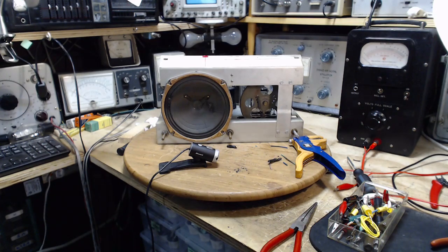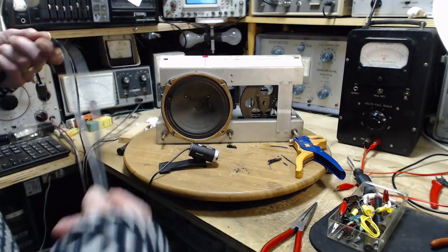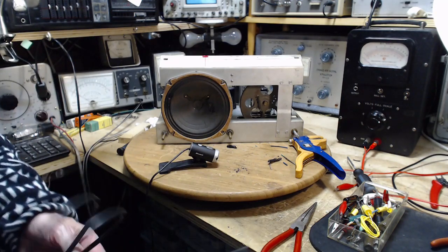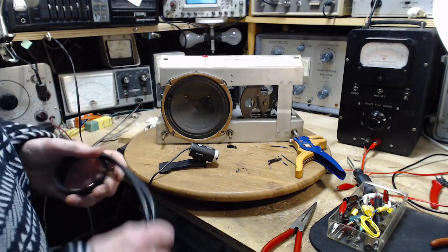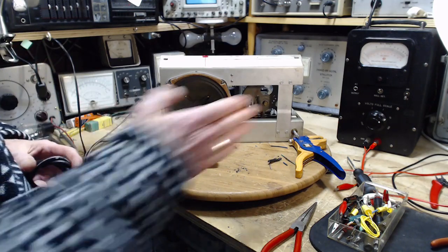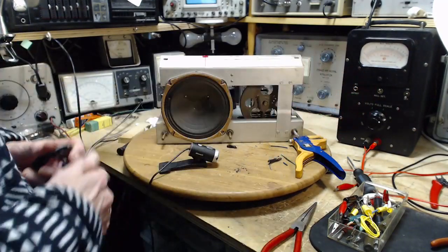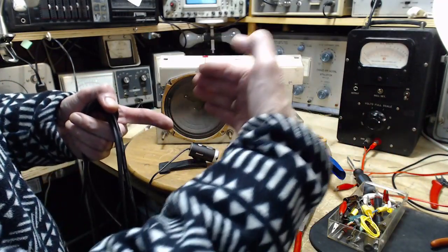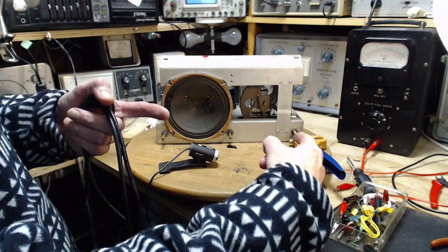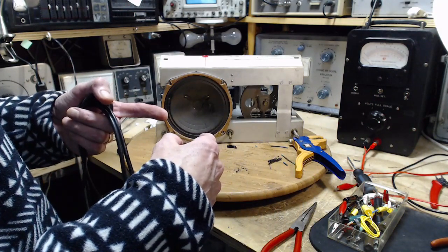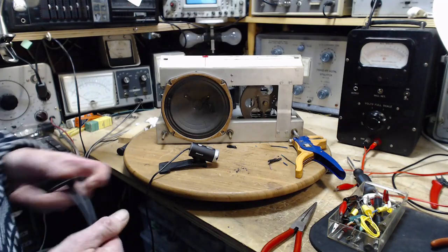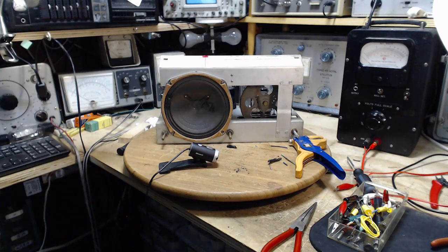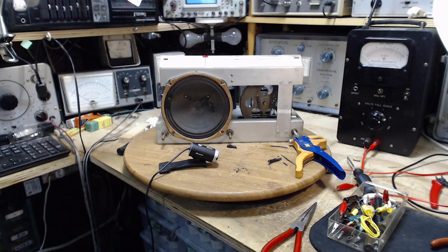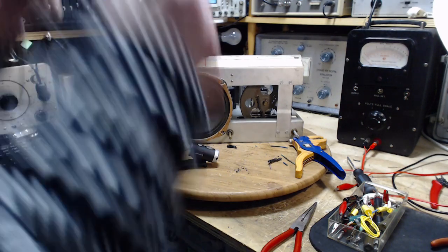So what do I do in my old job? I write a little report on this cable failure. Stick it in a file. Six months later, there'll be another cable failure on the same circuit, on the same electrical run, maybe even the same section of cable, might be a kilometer long section, broken into 50 and 100 meter pieces. One of them blew a year ago, next one blows. I get out my old file from the last one, I look at the pictures, I look at the stuff. Hey, it's the same thing again, whatever the thing is. And that's how I taught myself how to analyze cable failures.